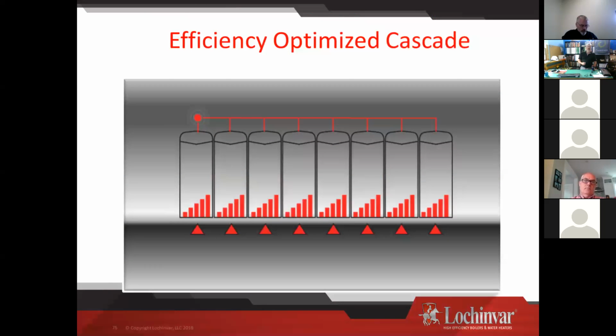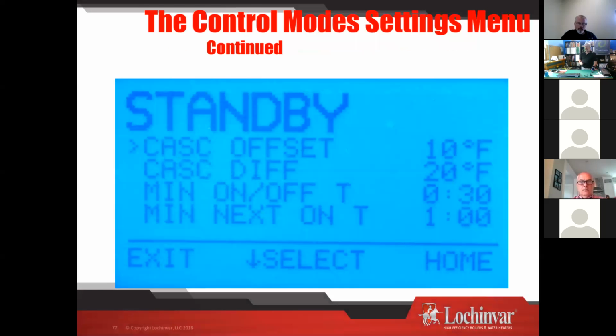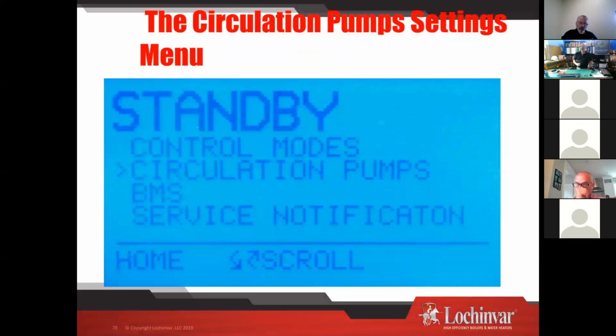We'll see this commercially. We see it in full flow applications, just keeping multiple boilers running instead of having flow through an off boiler and those types of setups. But that's more of a commercial application. Cascade offset and differential works just like our regular space heating offset and differential. Where do I go above? Where do I go below?